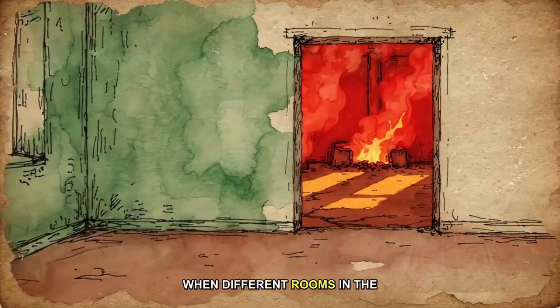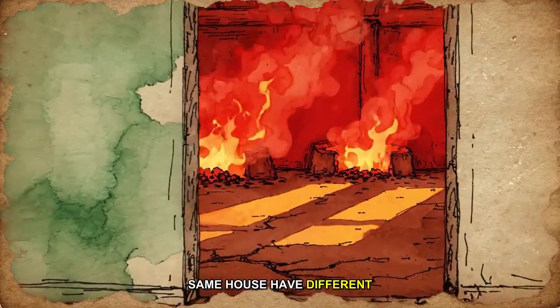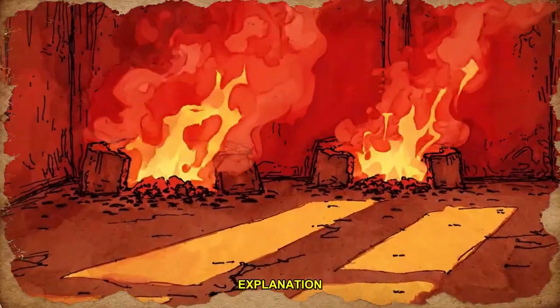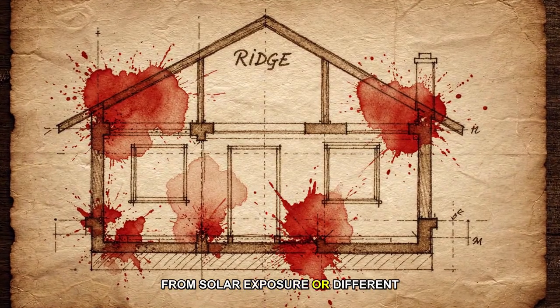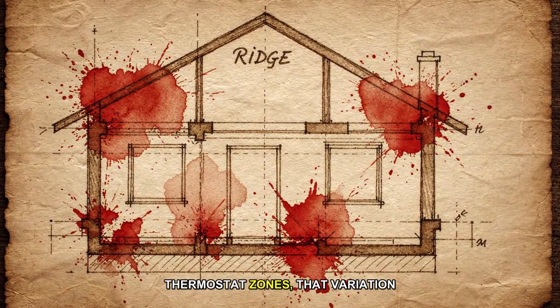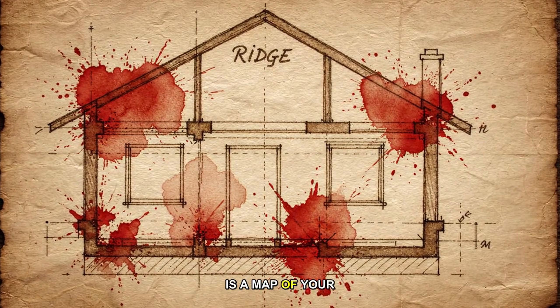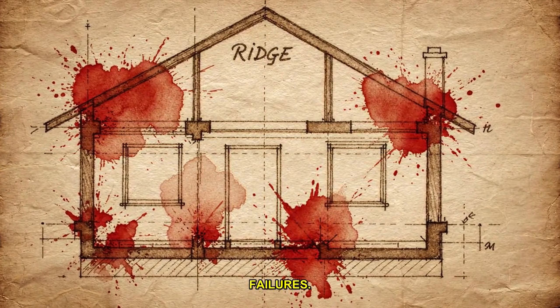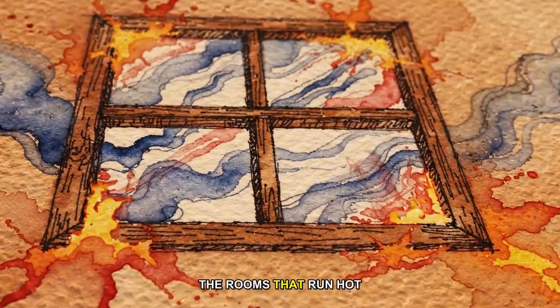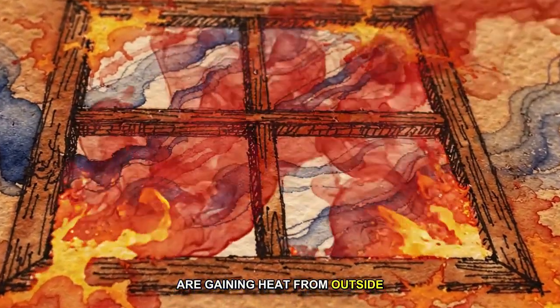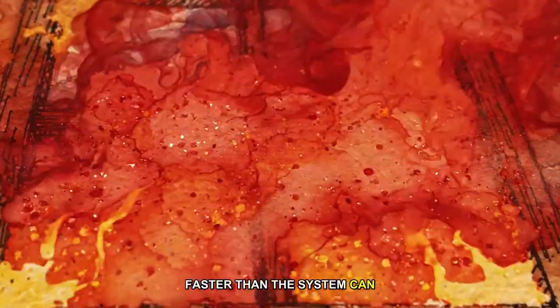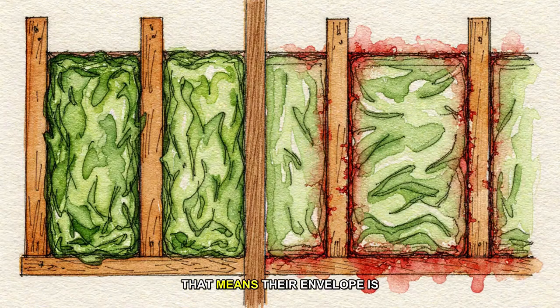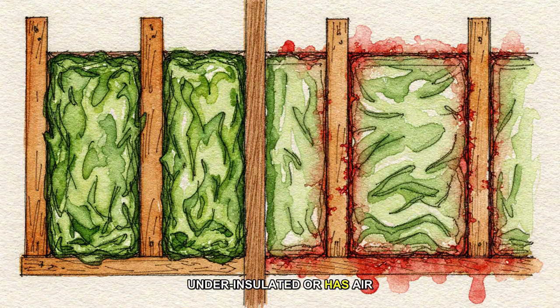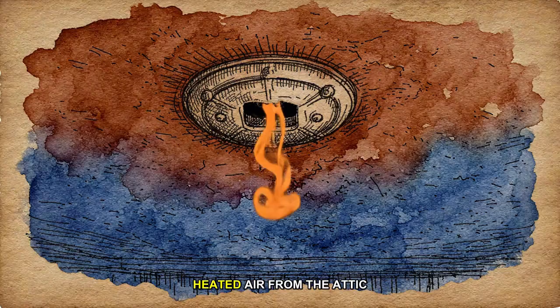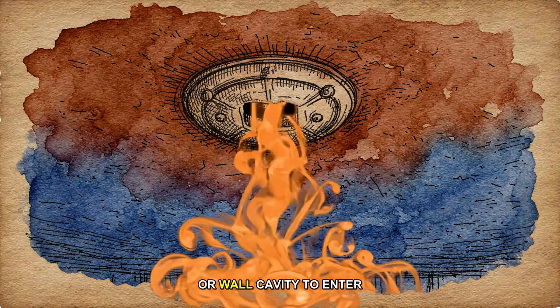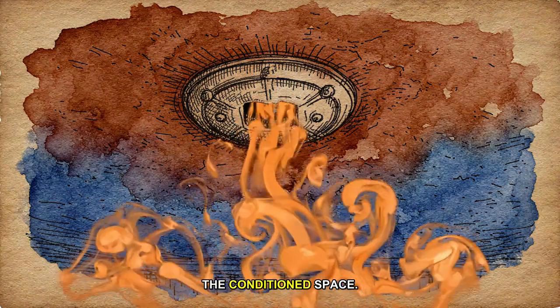When different rooms in the same house have different temperatures, without clear explanation from solar exposure or different thermostat zones, that variation is a map of your envelope failures. The rooms that run hot are gaining heat from outside faster than the system can remove it. That means their envelope is under-insulated or has air leakage that's allowing solar-heated air from the attic or wall cavity to enter the conditioned space.